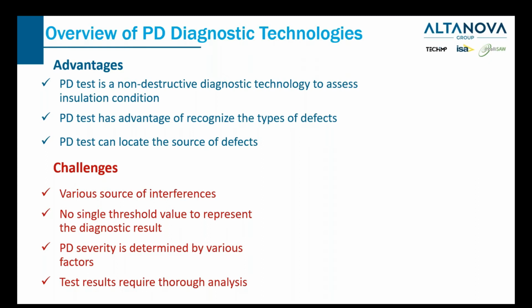testing technologies. I always use tan delta or dielectric loss as an example. Dielectric loss can measure a single value for an equipment. So that gives an overall performance of that equipment, but it cannot tell what type of defect we're looking at, or which component in that system. If we're testing a cable, we don't know where exactly the defect or the weak spot is with the dielectric loss measurement. But with PD test, first we can recognize what type of defect we're talking about.